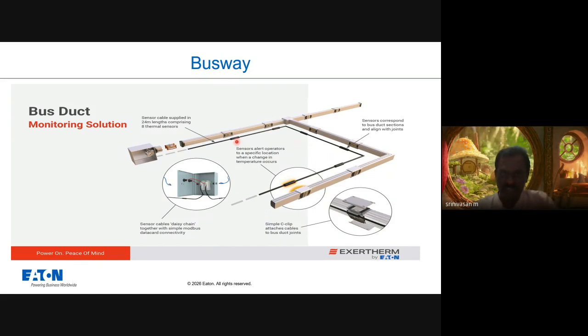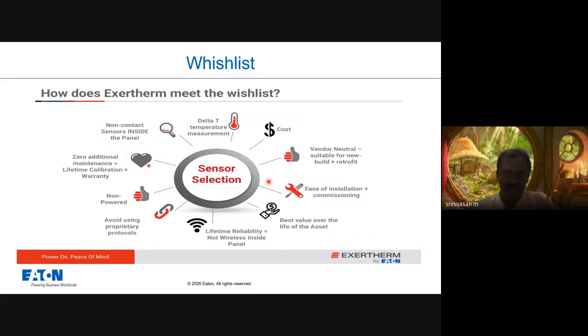So that is our wish list. As I said earlier, the good points are that it measures the temperature 24/7, it does not require any auxiliary power, and it enhances the safety of the switchgear. As a preventive measure, we can use this wired thermal sensor system anywhere, like LV and MV switchgear, busway, and even PDU and UPS.